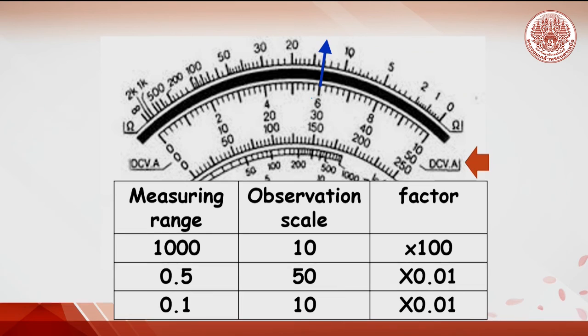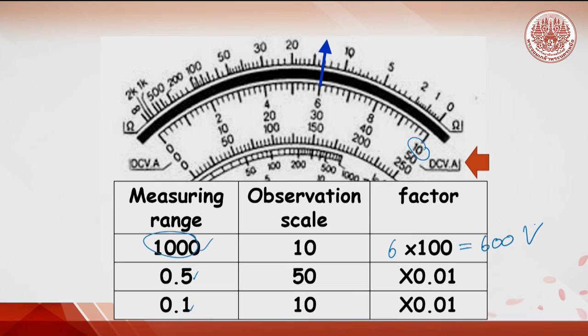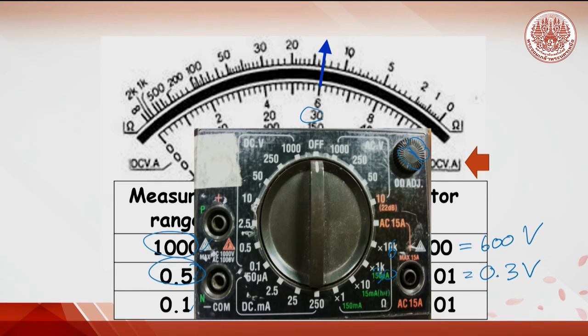For other measuring scales like 1000, 0.5, and 0.1: if measuring at 1000, look at the full scale of 10. The actual voltage is the reading times 100, so 6 times 100 gives about 600 volts. If the measuring range is 0.5, look at the scale of 50. After reading, multiply by 0.01 to get 0.3 volts. Finally, after reading, do not forget to turn the selector knob to off to maintain the battery in the multimeter.